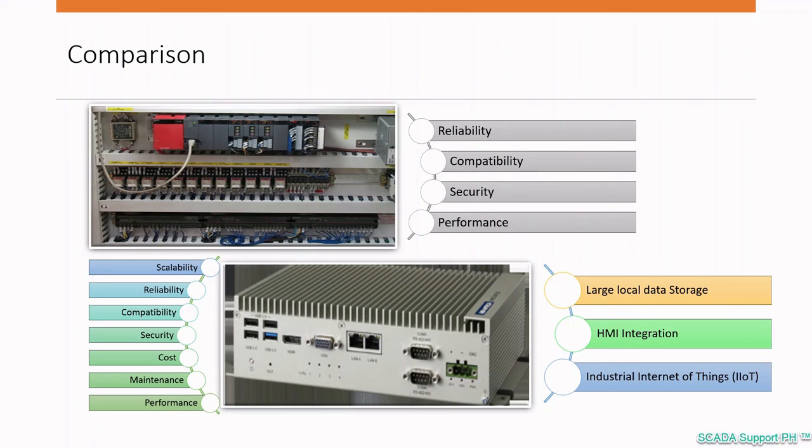The most robust solution consists of two embedded PCs with solid-state drives running industrial-grade software packages. The first PC is configured as the primary data concentrator, while the second PC runs the SC or grid controller programs, as well as engineering and analytics programs, and would also serve as the backup for the first PC.